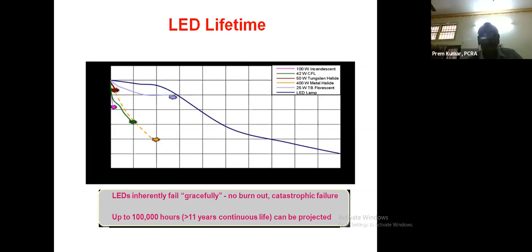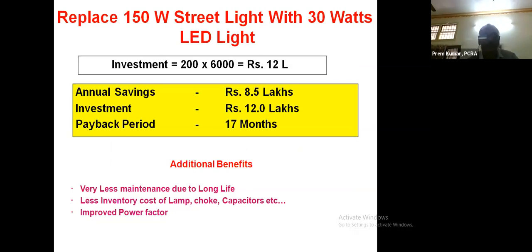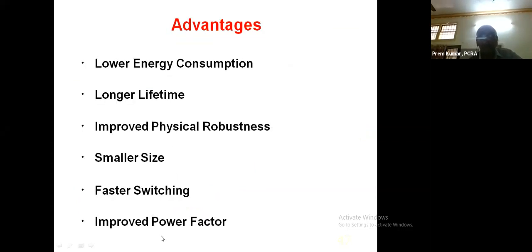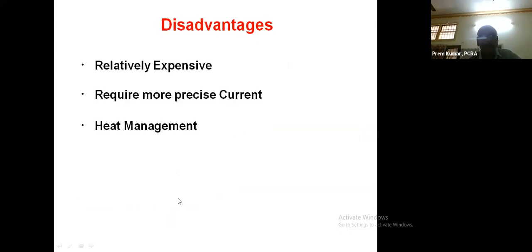Still, why does LED fail? We'll see as we move forward. Replacing a 150 watt street light with a 30 watt street light, you can see the wattage reduction. You get the payback in 17 months. Very long life, very less maintenance, so the inventory cost of lamps is also reduced. Your power factor is improved, and there are no touch shocks. Advantages: long life, improved power factor. But it has only one disadvantage: heat management is a problem.